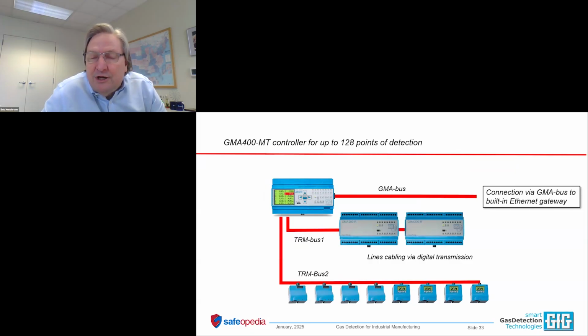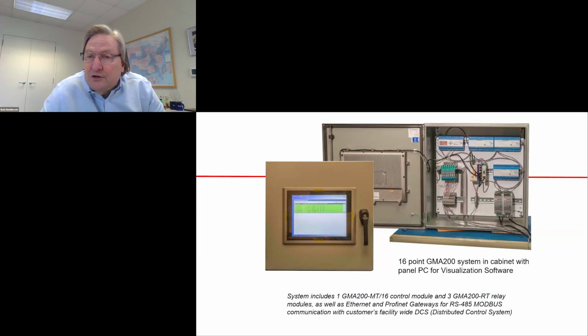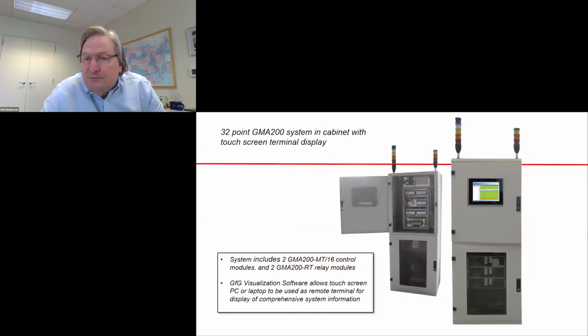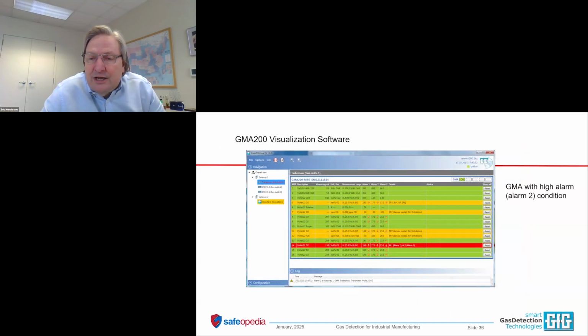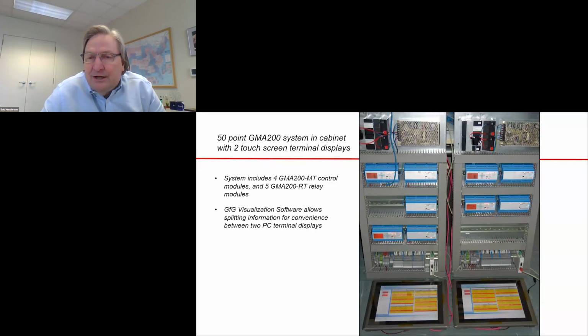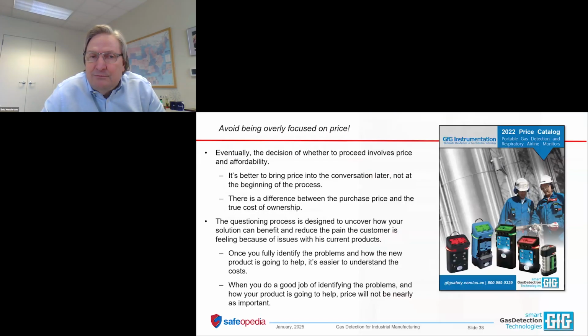And we have various levels of sophistication and size in terms of how many transmitters we can handle with a particular controller. This one is capable of handling up to 128 transmitters plus additional modules, and you can plug it into additional controllers. If you need a 500-point system, it's pretty easy to get there. Here's just to show you what it looks like. Here is a 16-point system in a cabinet with a touch screen PC built into the door. Here's a 32-point system in a floor standing cabinet. And here's an even larger 50-point system. So you can see how readily these systems can be scaled up.